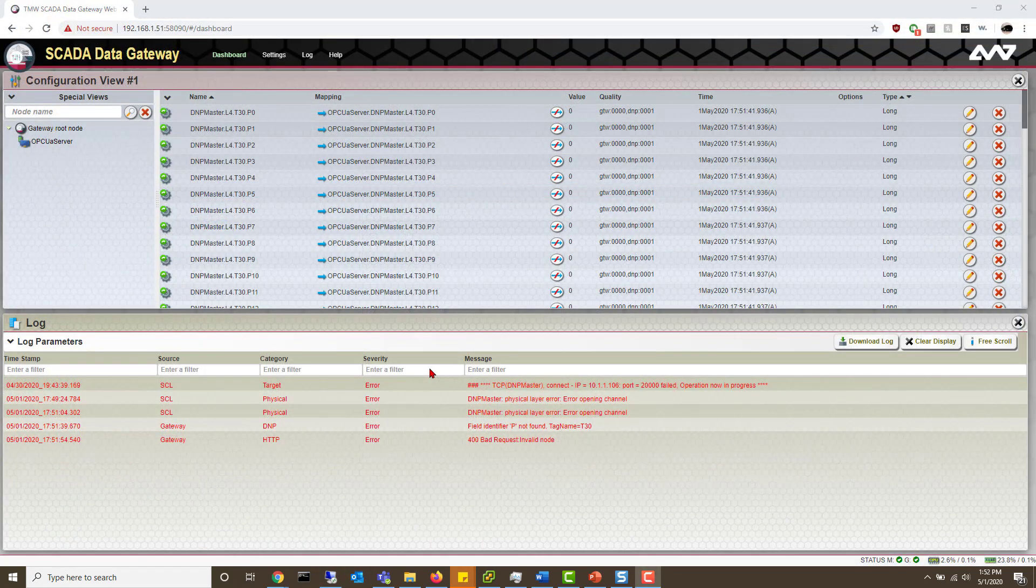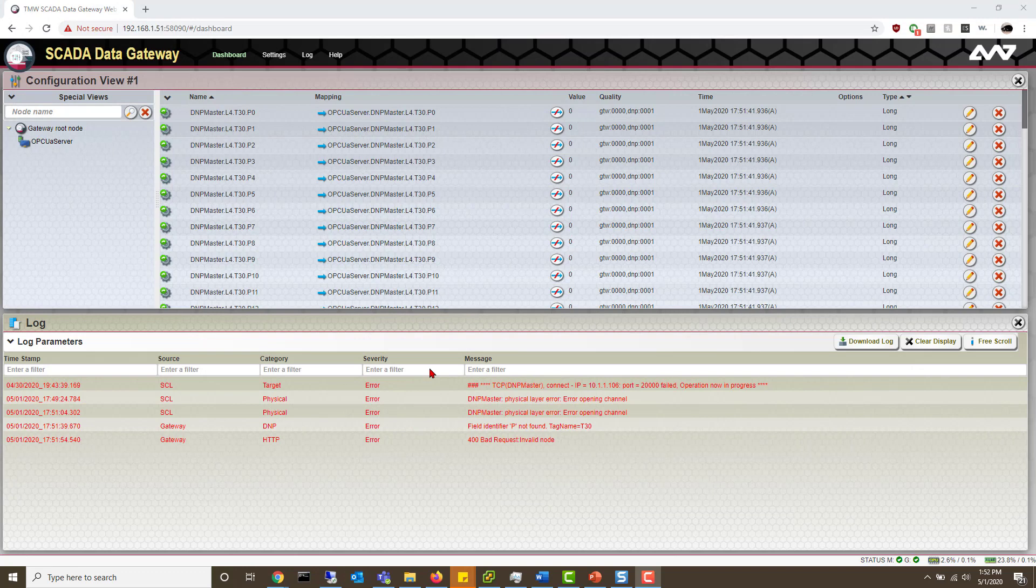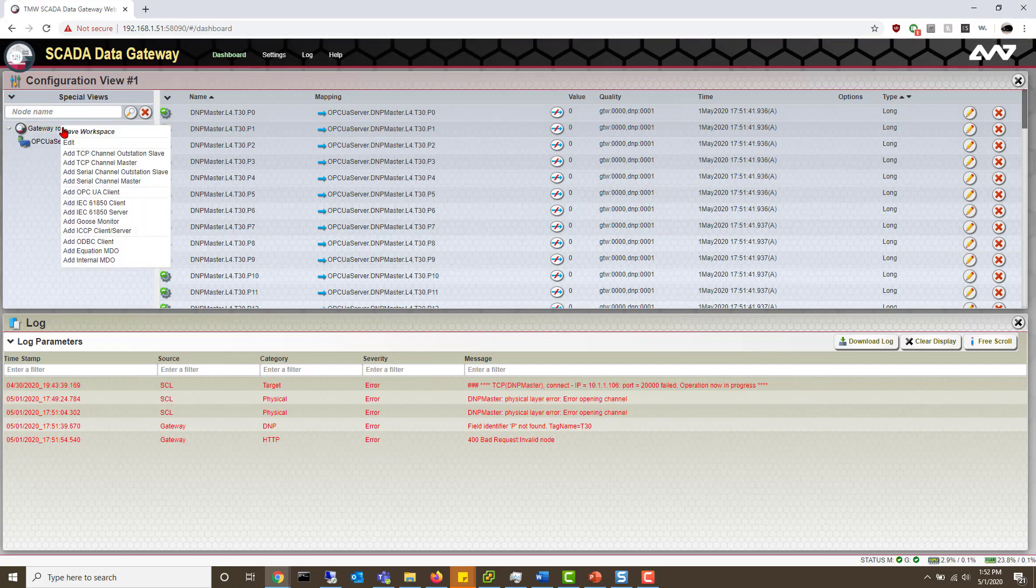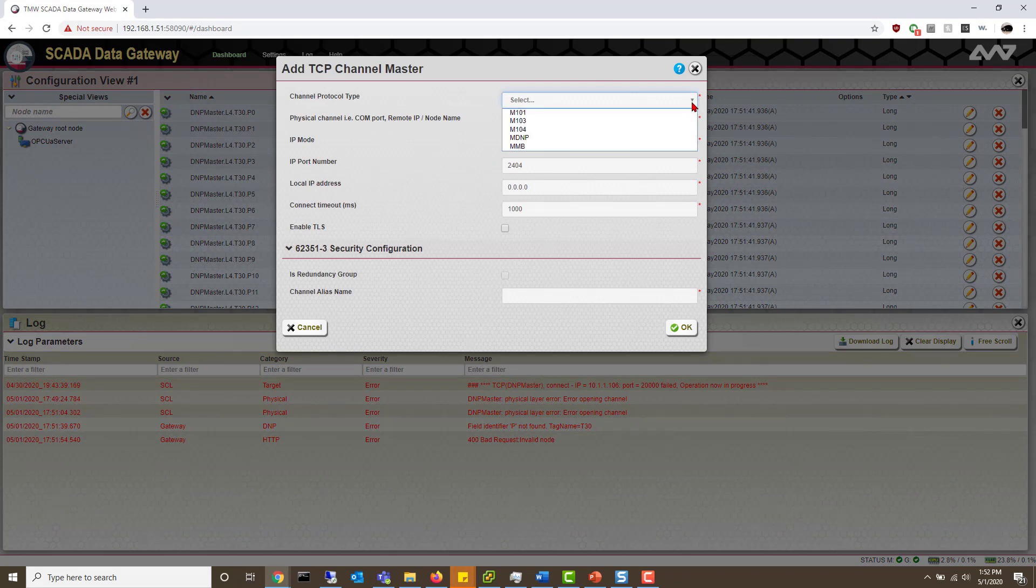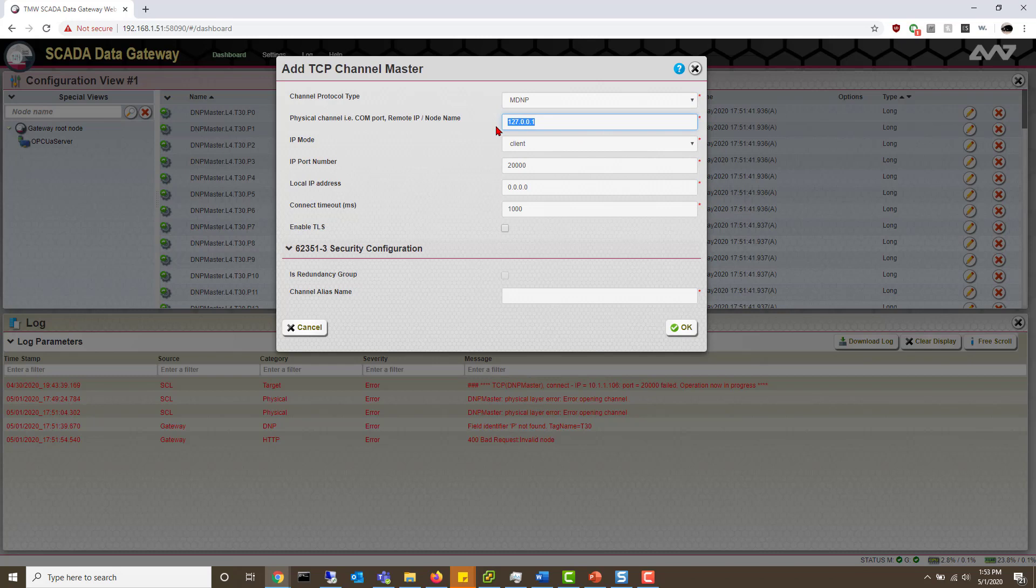Now that we have our DNP3 outstation setup in test harness, let's create the master in our SCADA data gateway. To do this, right click on the node, root node, to add TCP channel master. Select the protocol, which would be MDNP, and then put in the IP address from the machine that you have test harness running on. For me that's 10.1.1.106.